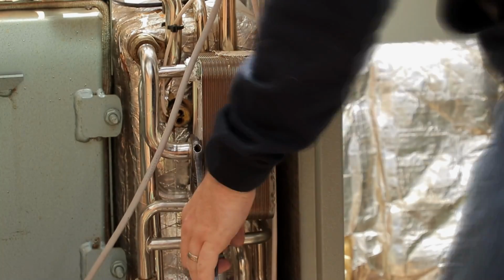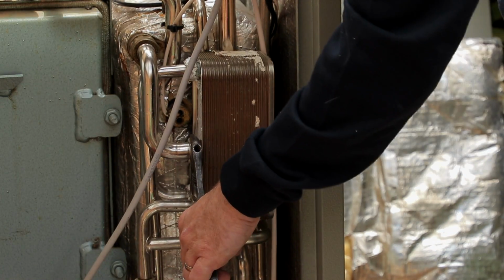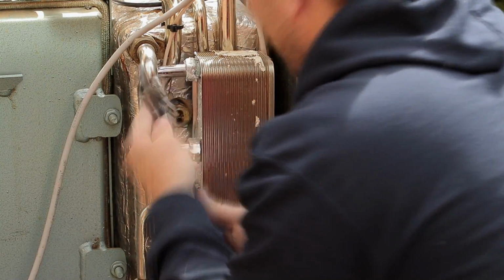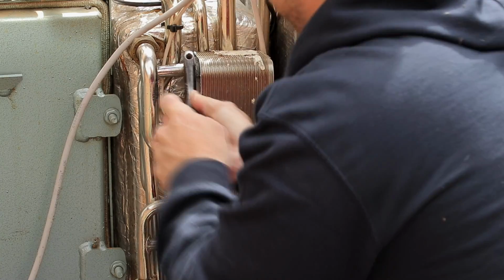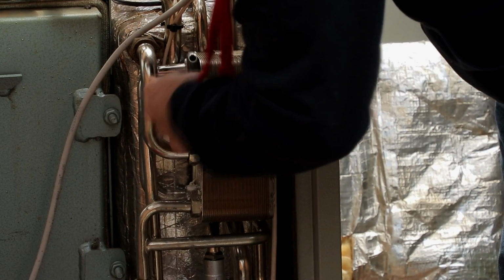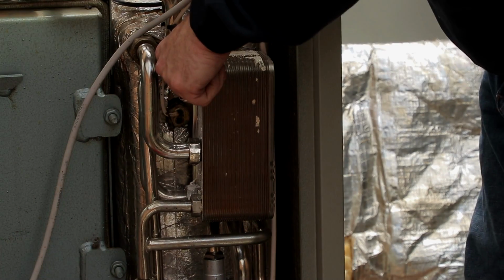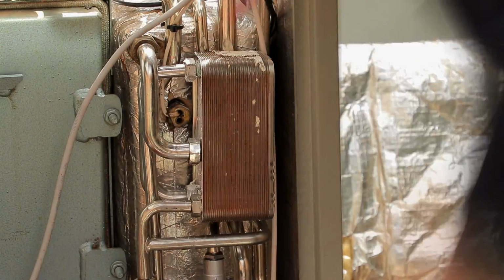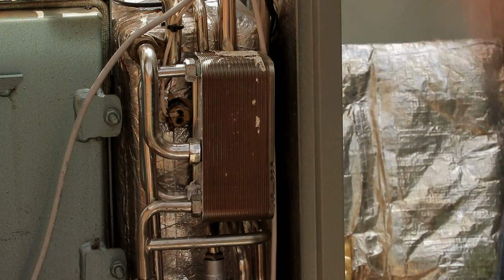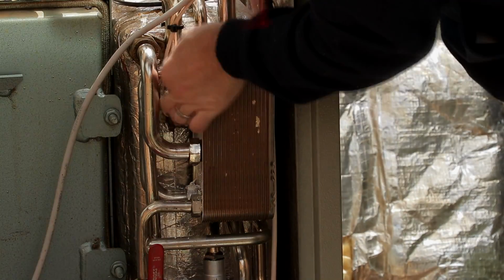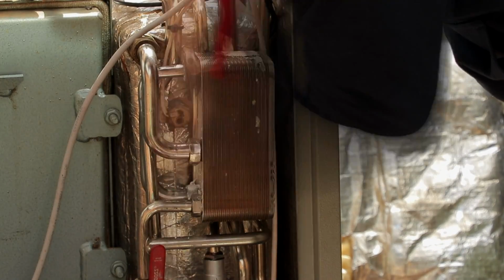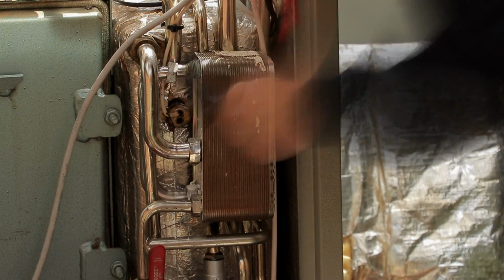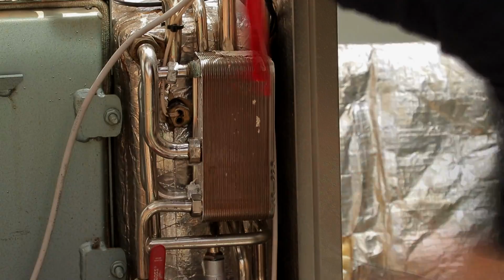So I wouldn't recommend this job for the novice. This is really a fairly advanced kind of plumber job, I'd say, made slightly more advanced if you want to do it without draining down the whole heating system. So number one, my workflow for this is to turn the boiler off to make sure all the pumps are turned off, and even pull the electric plug out of the boiler. Then I'll turn all the valves off to everything, including pump valves, and of course the cold feed in.